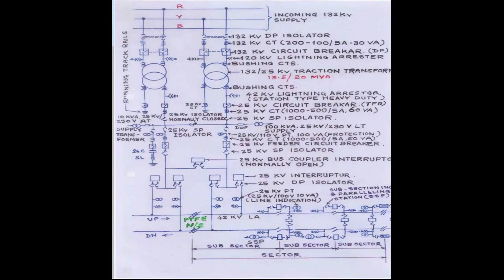So our main intention is protecting this transmission line. And what we have understood is protecting the transformer and this three-phase transmission line. This three-phase transmission line is protected by the state electricity board as well as from your traction substation. So this would be a three-phase protection. Here it would be two-phase. And you will have CTs located here. You can see the CT windings. Using this winding, we will provide single phase differential protection to this transformer also.